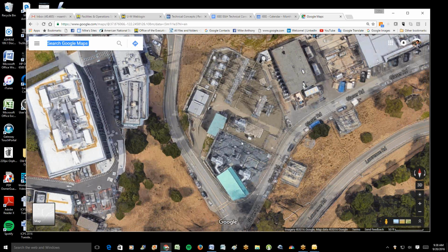So we have a couple of designs we've been looking at. The limitation is what we call our switch station 1, which is right next to the 115 kV yard, and it's limited by the 41 MVA. So there's a thought to put another switch station in the area, run the transformers in there, and then feed back out of there to an additional switching station to try to increase our capability.